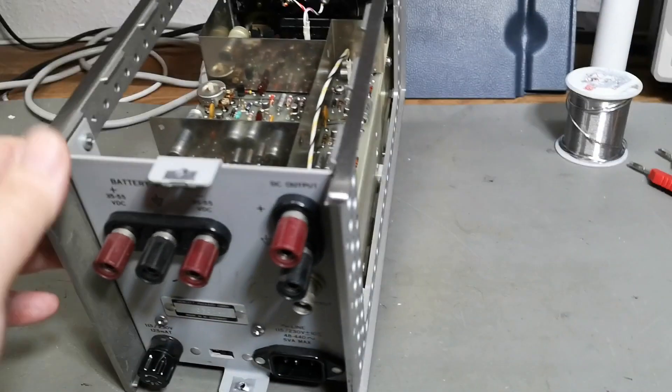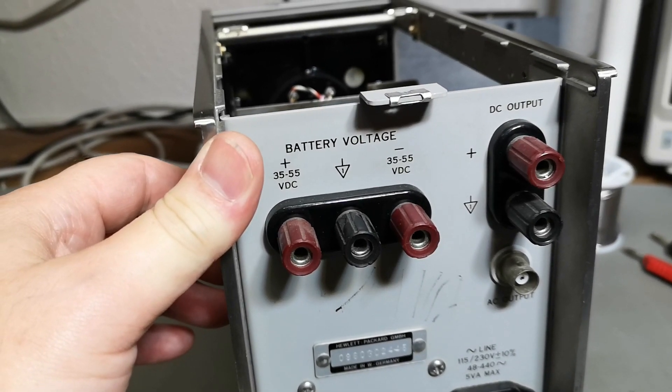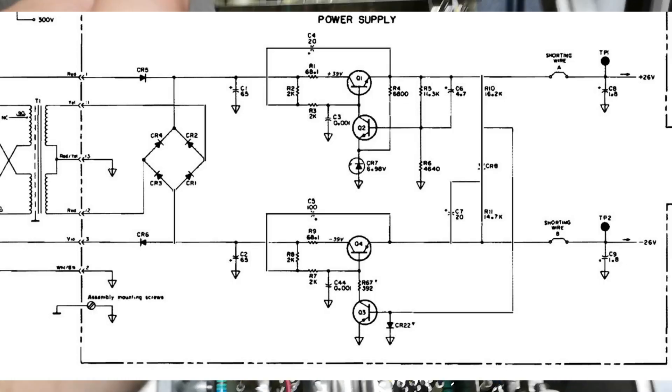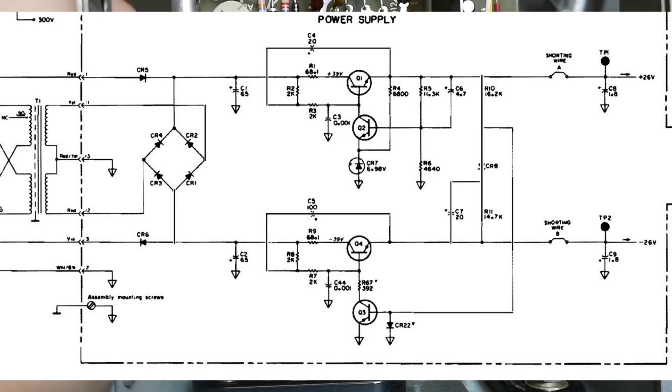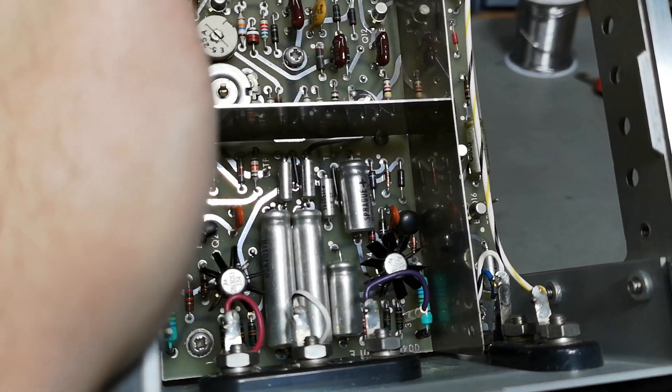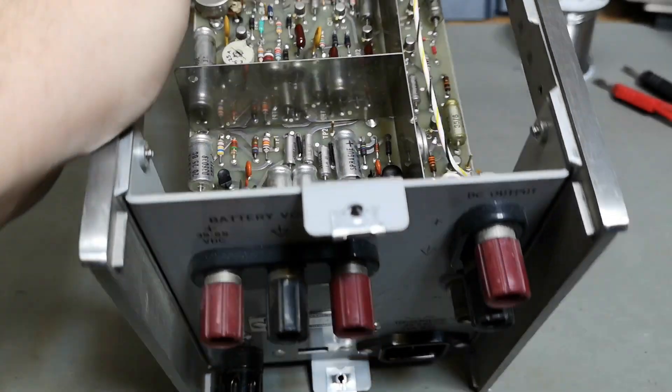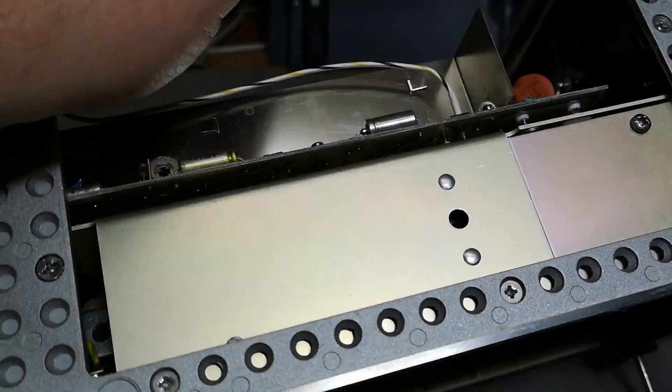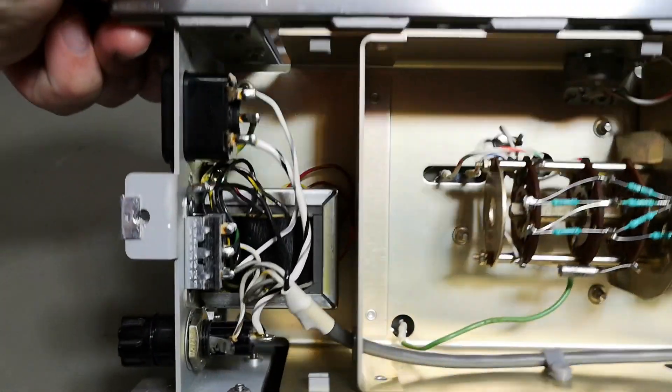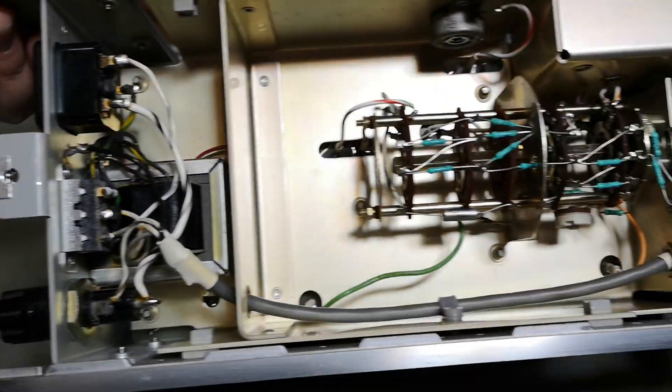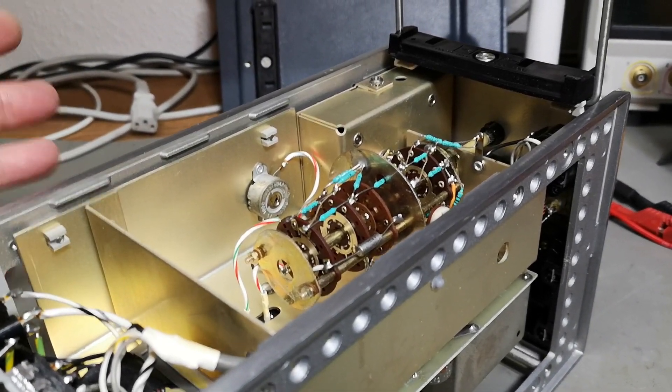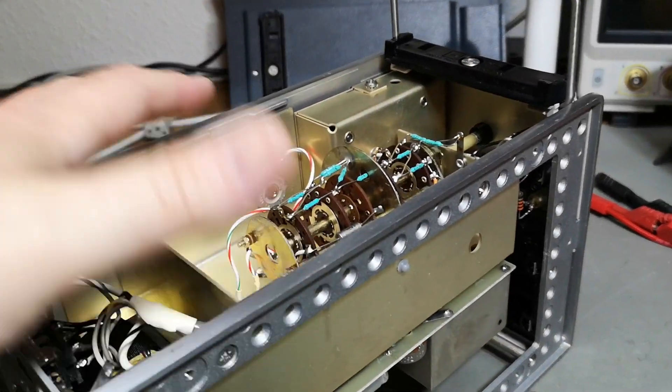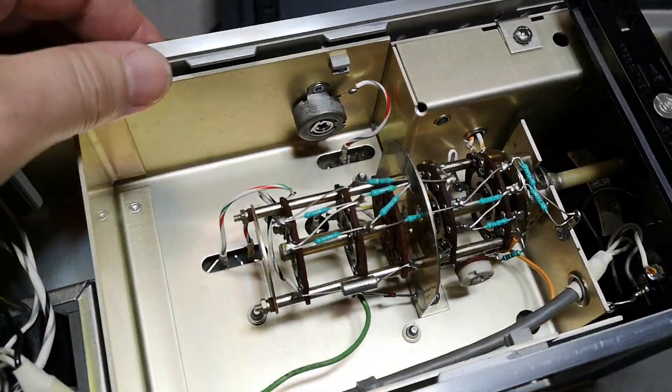I forgot to say that the external battery voltages go into a double linear power supply and the voltage internally is plus-minus 26. But this is not a low-drop regulator, so you need a lot of extra volts. That is why the minimum voltage is 35. There's a tiny little mains transformer down here, and the power consumption should be around 10 watts for this unit. There isn't any other shieldings or metal plates and stuff like that. It's much more simple and cheap to manufacture.